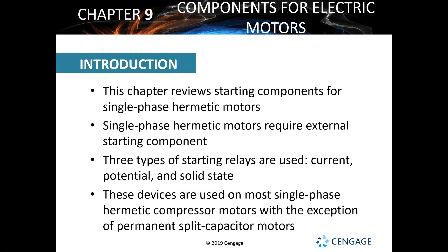So, starting relays for single-phase motors. Again, single-phase motors, remember, you only have to have 3 things as far as wires going to them. You need a common, a run, and a start. Now, these relays, they're going to be your main thing that's going to actually start up your motor. All right, there's a couple of different styles of them depending on what kind of motor we've got. But talking about this one specifically for single-phase, it has to have a means of dropping the starting winding out of the circuit. There's got to be some way to disconnect it and just have the run winding operating.